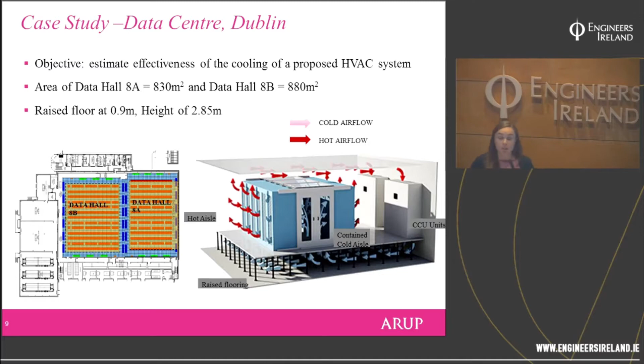In this example, we looked at the normal mode of operation, with a number of cooling units on the top and bottom of the data center, first checking whether this would perform optimally with all units running. We also considered an emergency situation where some cooling units might be turned off or broken. In both cases, we found the data center would be fine, the specified HVAC would perform efficiently, and there wouldn't be overheating. As additional work, we also did an external flow analysis.